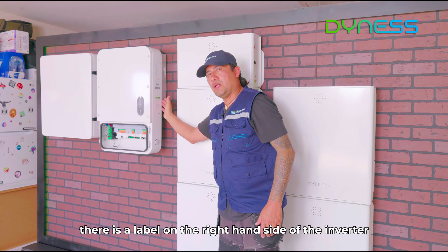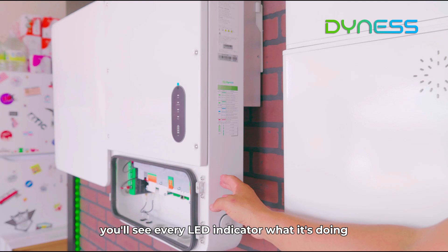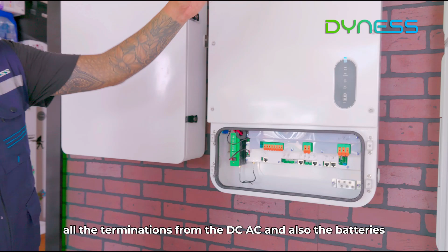Once everything is communicating and talking, there's a label on the right-hand side of the inverter. At this point, you'll see every LED indicator, what it's doing, what the hybrid inverter is doing, all displayed here. Once on and commissioned, everything's working properly. We'll go ahead and turn on your DC strings. It's in the off position, down to the on position. Once all the proper voltage testing, all the terminations from the DC, AC, and also the batteries are all in place, we are good to go.